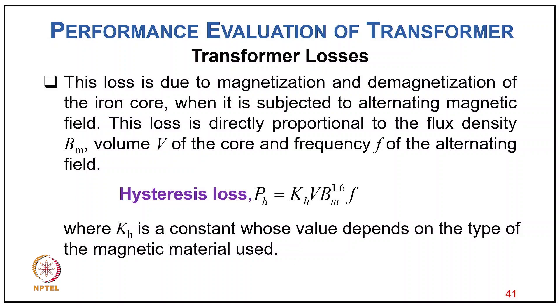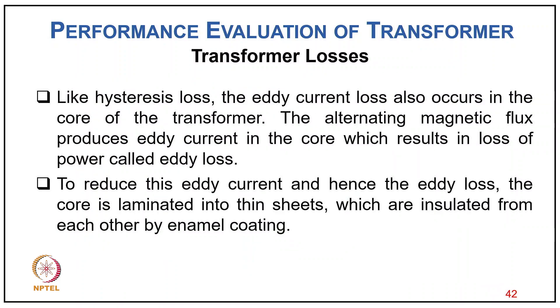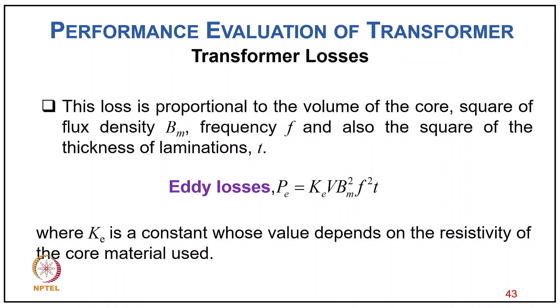Hysteresis loss Ph = Kh × V × Bm^1.6 × f, where Kh is a constant depending on the magnetic material used. Similarly, eddy current loss also occurs in the core due to alternating flux inducing eddy currents, and to reduce this loss, the core is laminated into thin steel sheets insulated from each other by enamel coating. Eddy current loss Pe = Ke × V × Bm² × f² × t², where t is the thickness of lamination and Ke depends on resistivity of the core ferromagnetic material.